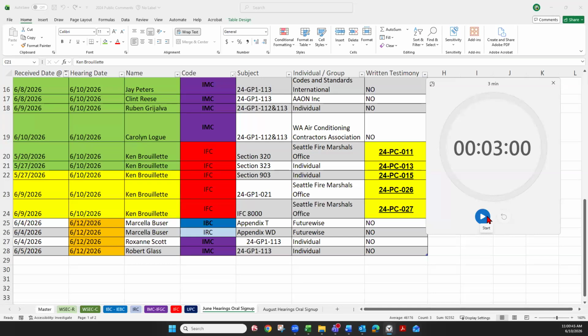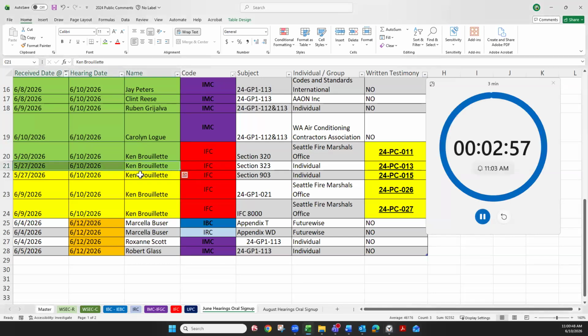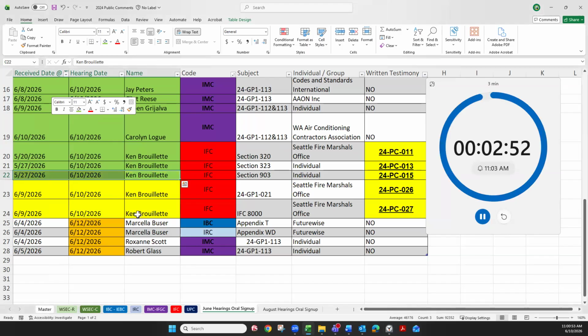I'm Ken Burlett, representing the City of Seattle Fire Marshal's Office. I'd like to address WAC 51-54A-0903. The 2024 IFC has a change in exception 1 stating that batteries are not required to have an automatic sprinkler system by section 1207 for energy storage systems. This was added because the current exception simply states 'batteries.' The problem is, based on the provisions in 1207, batteries that are part of an energy storage system may require an automatic fire sprinkler system, and not including this base code language exception in our Washington State amendment will cause confusion.